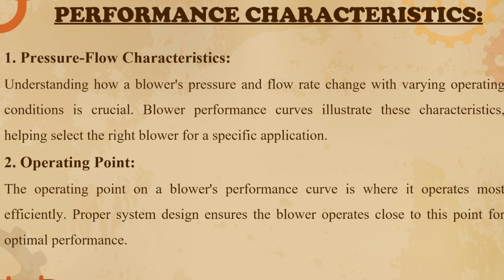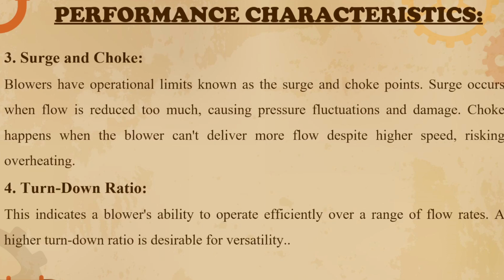So for pressure flow characteristics, understanding how a blower's pressure and flow rate change with varying operating conditions is crucial. Blower performance curves illustrate these characteristics, helping select the right blower for a specific application. Second characteristic is the operating point. The operating point on a blower's performance curve is where it operates most efficiently. Proper system design ensures the blower operates close to this point for optimal performance.